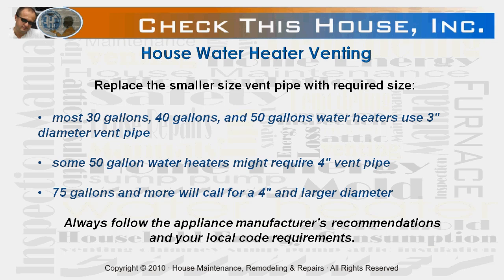Remember to always replace the smaller diameter vent pipe with one that matches your new appliance requirements. For example, most 30, 40, and 50 gallon water heaters use three inch diameter vent pipes. Some 50 gallon water heaters might require a four inch diameter vent pipe. 75 gallons and more will call for a four inch and larger diameter. Always follow manufacturer recommendations and comply with your local code requirements. Never downsize the vent pipe.